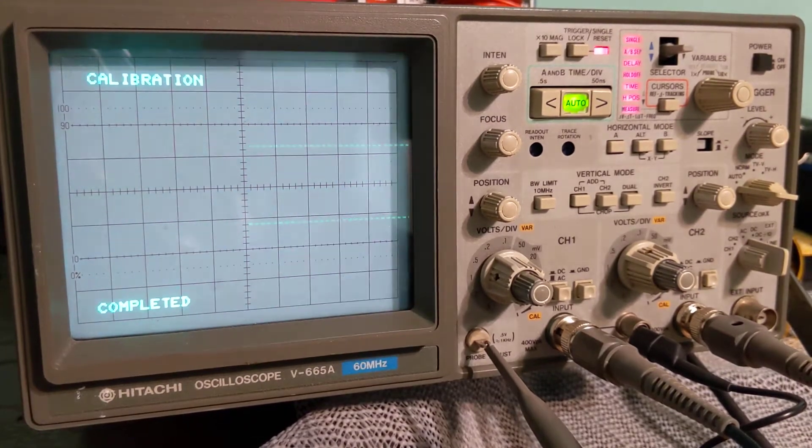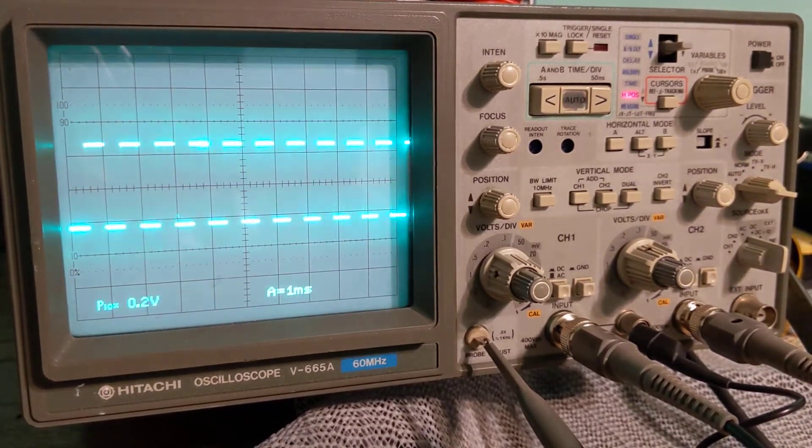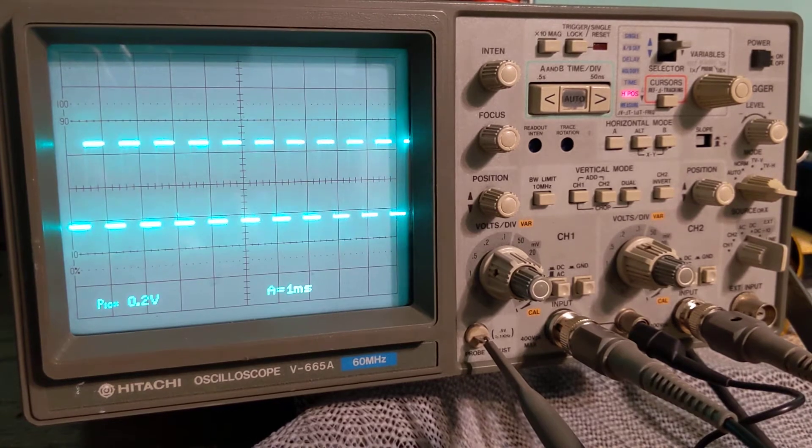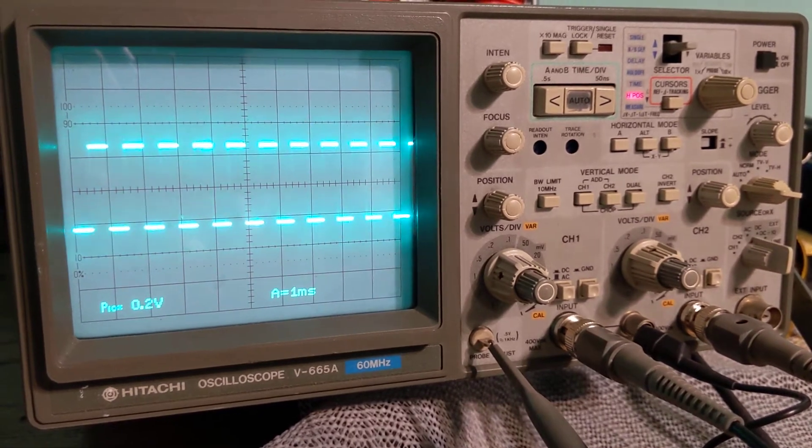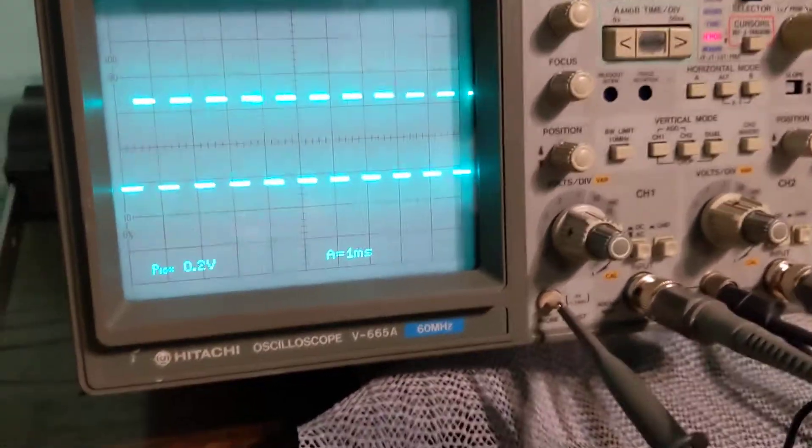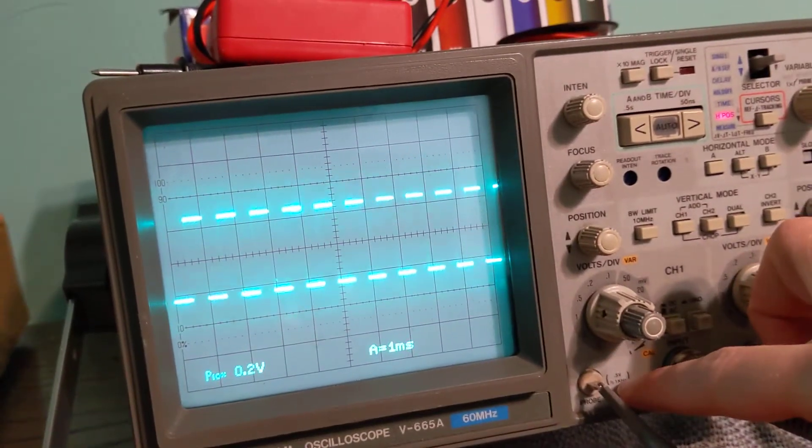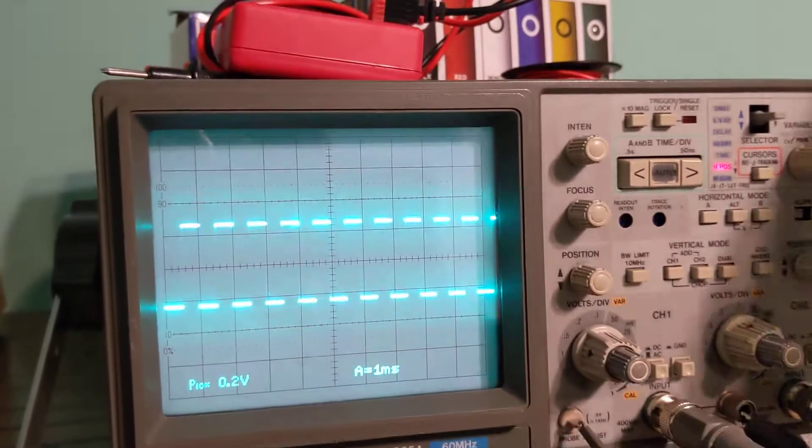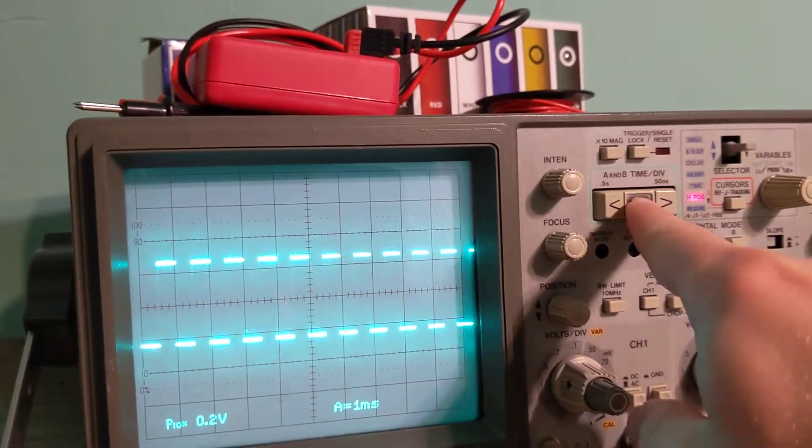Calibration completed. Alright, so what this should look like is a square wave with 0.5 volts at 1 kilohertz.